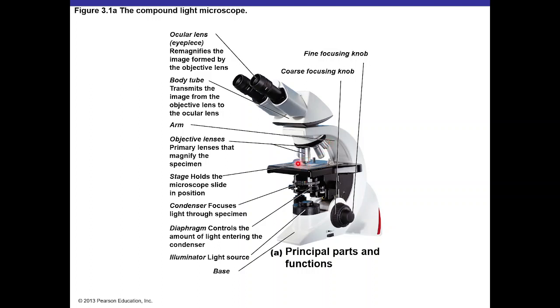The objective lenses come in several sizes and magnify the image at different levels. Below the stage is the condenser lens, which gathers the light and directs it through the glass slide and into the objective lens. Below the condenser is the diaphragm, which allows you to reduce or increase the amount of light passing through the condenser to improve sharpness and contrast.